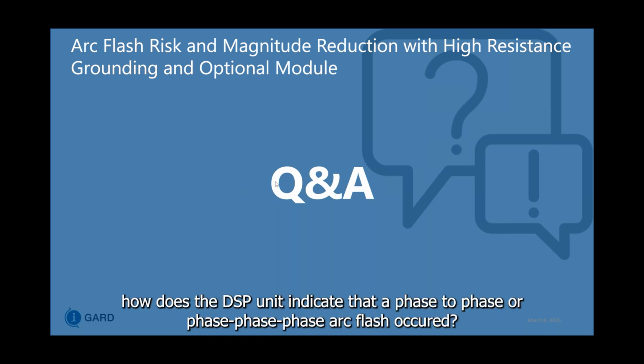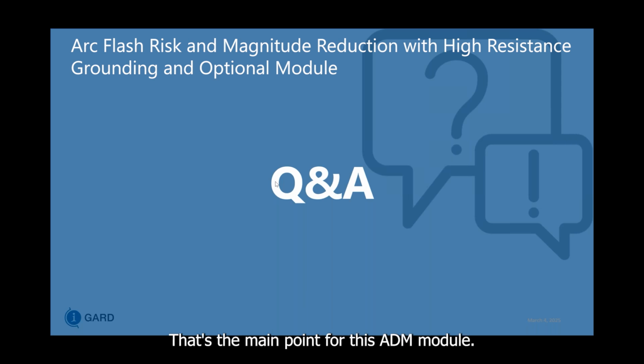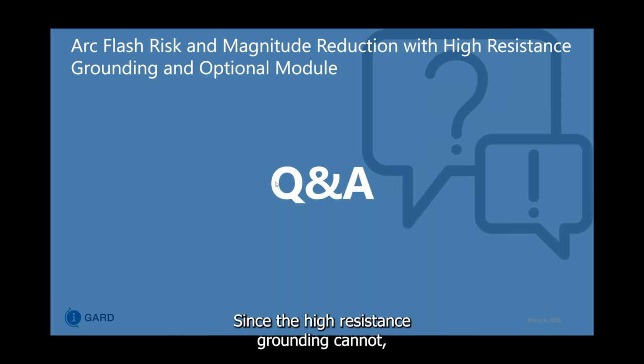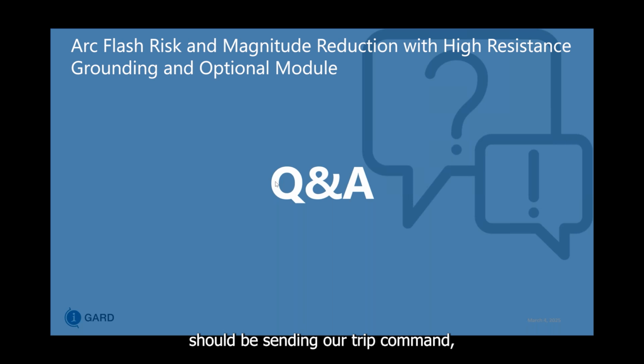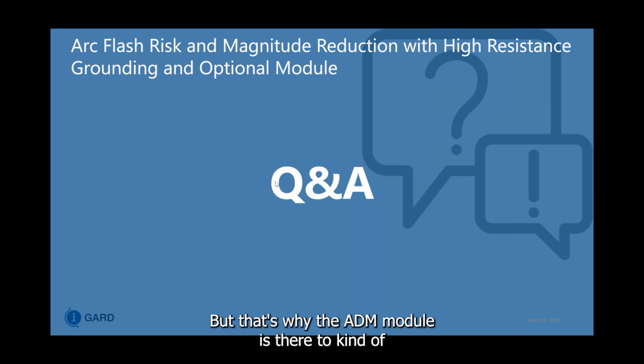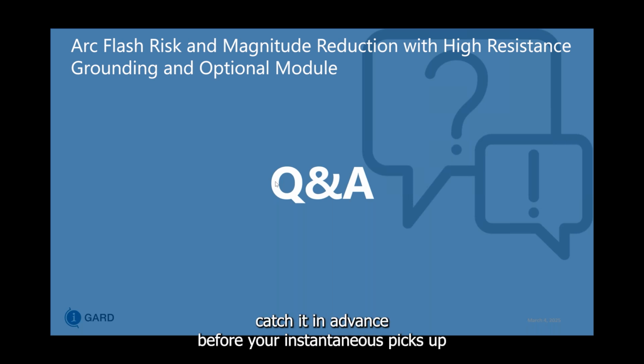magnitude. How does the DSP unit indicate that a phase-to-phase or phase-to-phase-to-phase arc flash has occurred? That's the main point for this ADM module, since the high resistance grounding cannot pick up the phase-to-phase and phase-to-phase-to-phase failures. Usually your instantaneous function of your breaker should be sending a trip command when it sees high levels of current, but that's why the ADM module is there to kind of catch it in advance before your instantaneous picks up on the fact that there's high levels of current so that we can just trip faster.